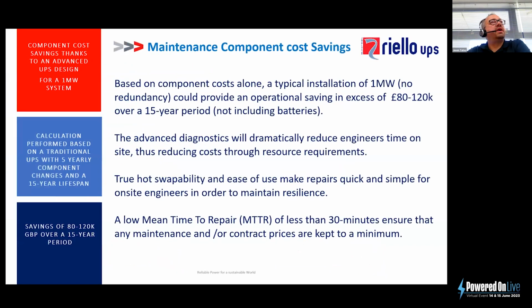So as you can see there, it's not just about the power. Based on component cost alone, because of the maintenance, a typical site could save in excess of 80 to 120,000 pounds over a 15-year period. And because of the advanced diagnostics, it significantly reduces engineers' time on site, thus reducing costs through resource requirements. True hot swappability makes it easy to use and quick to repair, and a low mean time to repair, less than 30 minutes, means maintenance and contract prices can be kept low.